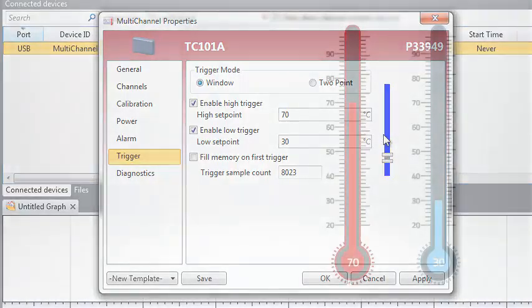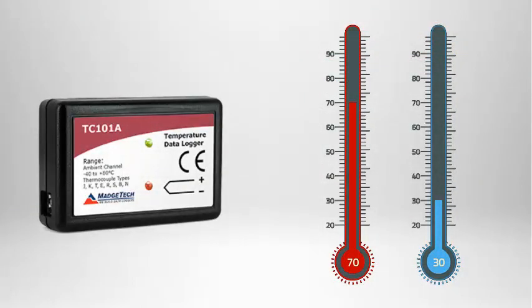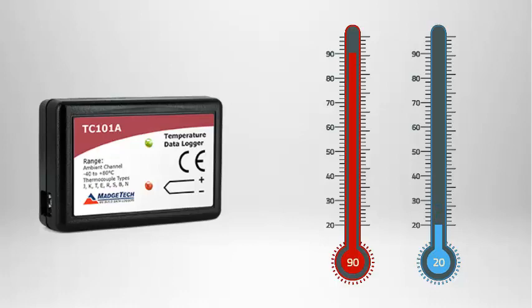With these example settings in place, once the device is started, recording will only begin when a reading is below the low set point value of 30 degrees Celsius or above the high set point value of 70 degrees Celsius.